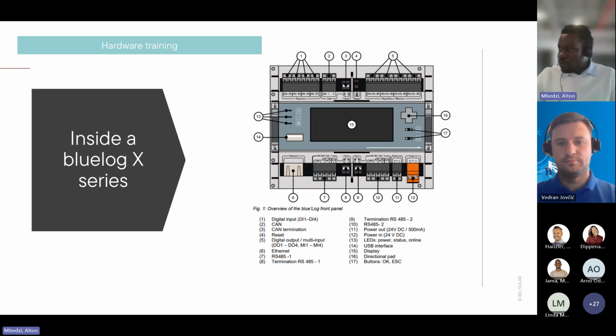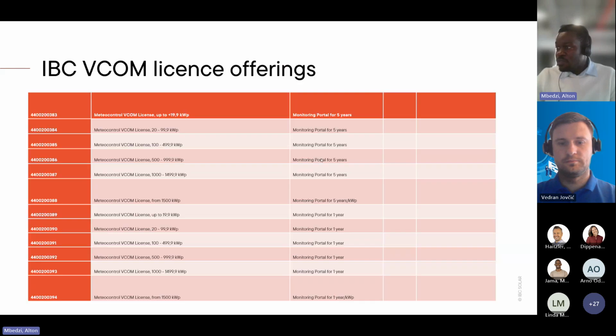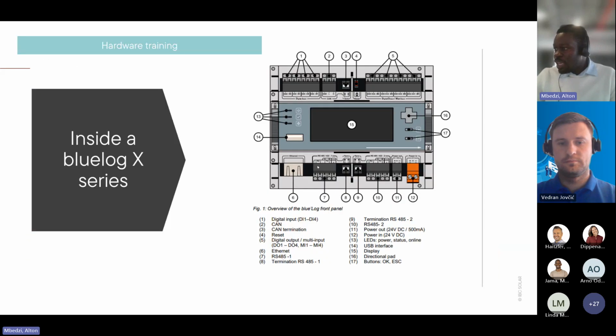If you look at your RS485, you have RS485 1 and 2. So you only have two RS485 interfaces to connect bus devices. What happens is you can connect your inverters, your energy meters, your string monitoring, your power analyzers, and sensors and meters can be queried together to communicate via Modbus on this.